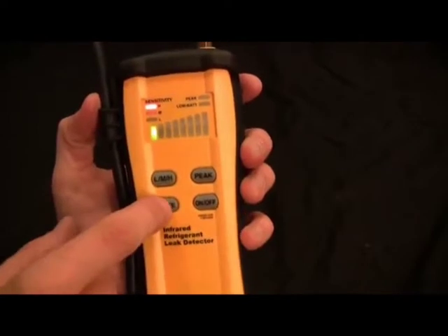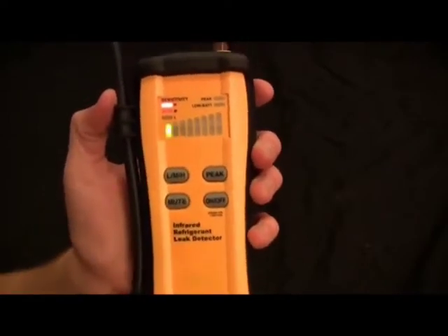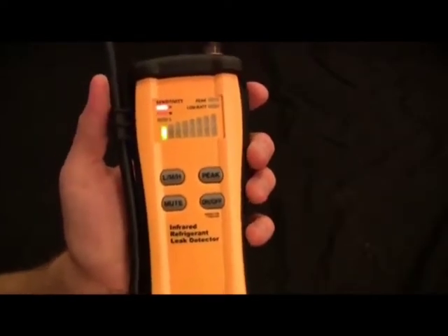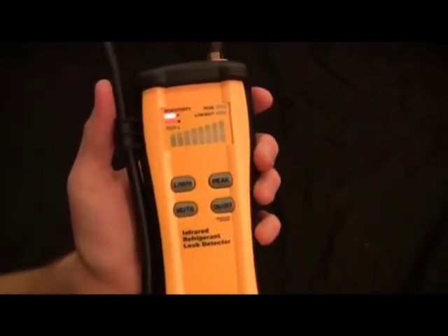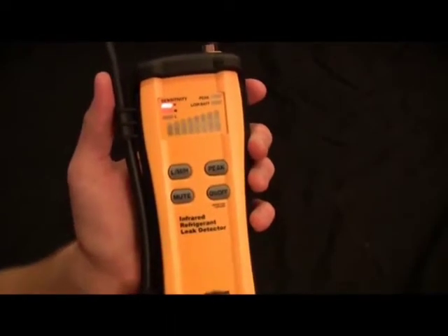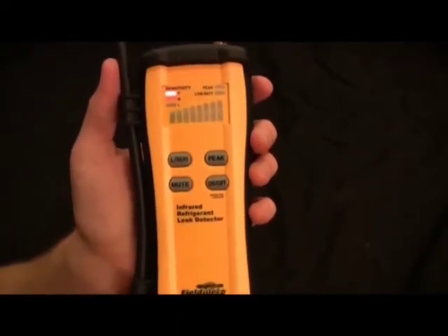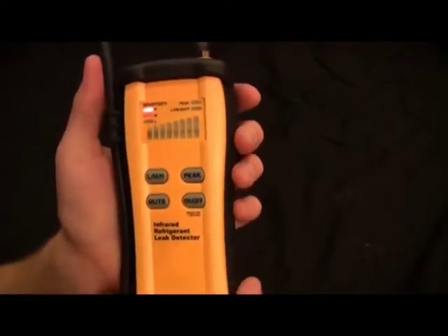So what we're going to do now is actually sense some leaks. I'm going to go ahead and unmute it. Now the first leak we're going to sense is our small leak, because it's only 0.31 ounces per year leak rate. So it's still a very small amount of refrigerant leaking out of this bottle. And this is our 134A right now. Let's go ahead and show you how it works.